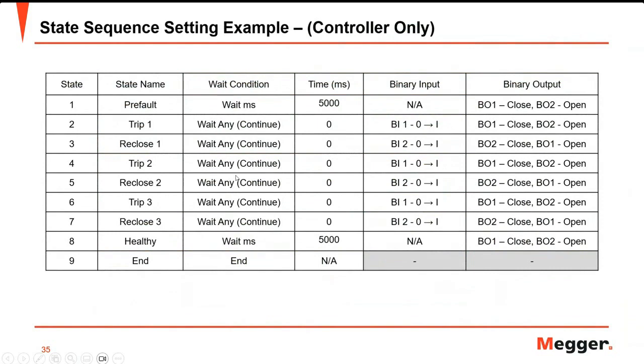We need to use the RTMS software and configure the state sequences for testing the auto-recloser. Here we have a table to summarize the configuration of each state. We have State 1, set for pre-fault — here is the wait condition and the time. These values may depend on your test requirements. The binary output is used to simulate your breaker status.